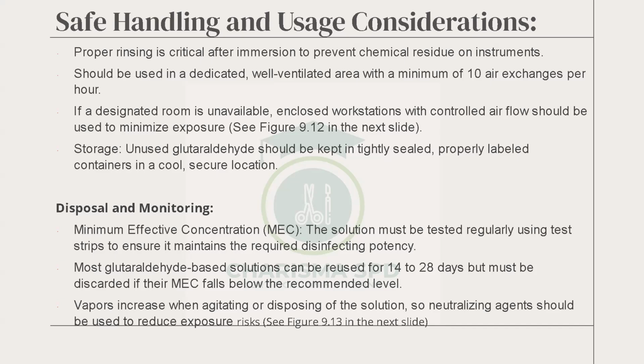Then we also have the storage. Of course, unused glutaraldehydes should be kept in tightly sealed, properly labeled containers in a cool, secure location. What happens is that when you pour the chemical from the gallon and maybe you are not able to pour all and there is some left, this is what we mean by shelf life or use life. Remember, we were talking about shelf life and use life. The use life is the one where you are actually processing, putting in chemicals, reprocessing instruments. That is the use life. But the shelf life is, of course, if it is not open at all, how long? Once you open it and you don't use all, the leftover falls under the use life, not the shelf life anymore, because it has been opened. I don't know if you understand me.